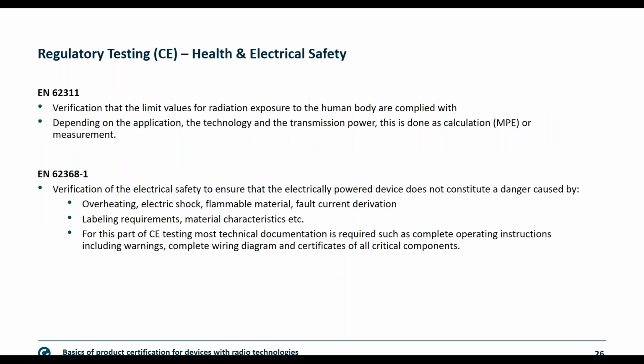On health and safety, briefly: two standards are given, though for health it's only one—EN 62311, covering radiation exposure to the human body via an MPE calculation or measurement. The electrical safety standard is 62368-1, a hazard-based standard. Engineers examining your product will test for sources of hazard to the operator: heat, sharp edges, flame, electrical shock—all of this must be respected.